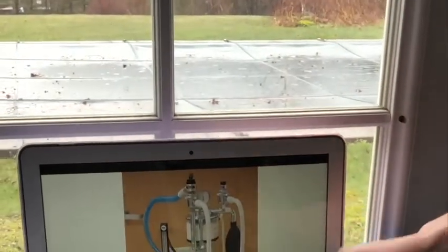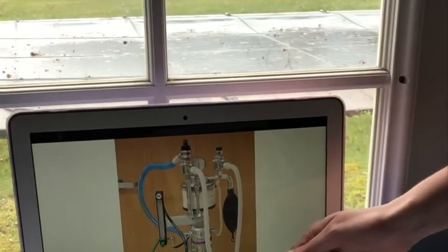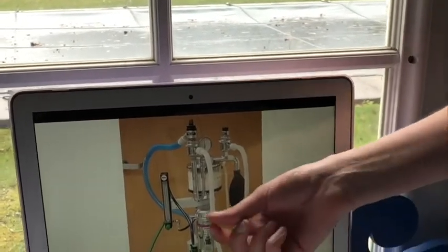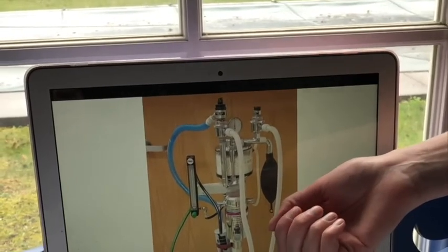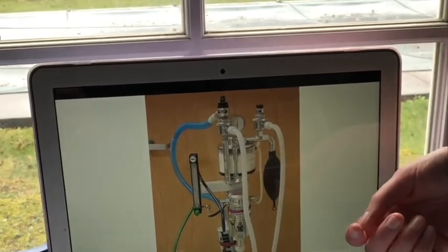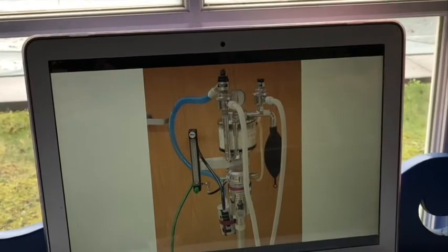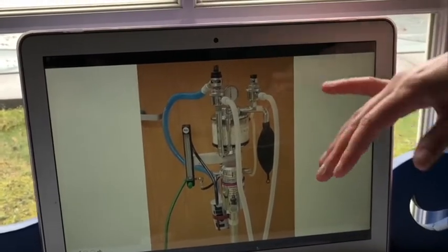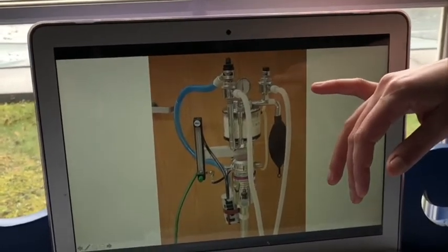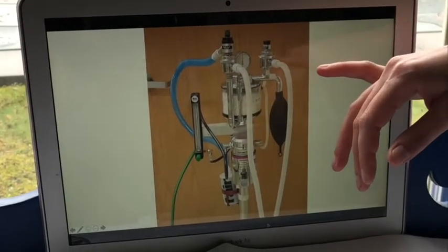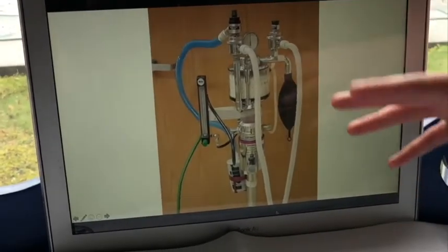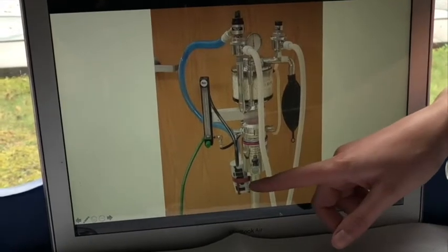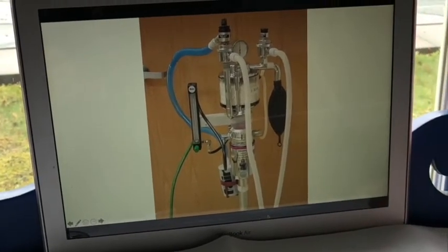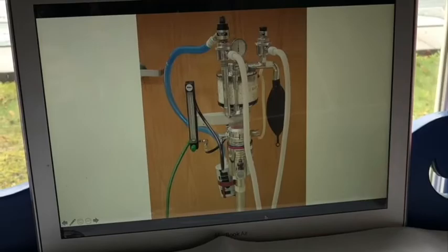So how we do that is that we have our pop-off valve open, and then we're going to occlude the patient Y piece again. And then we're just going to turn on the flow meter to about 4 liters per minute. And then just making sure that that is staying steady, that the pressure manometer is not increasing by more than 2 centimeters of water, to make sure that the scavenger system is working appropriately.